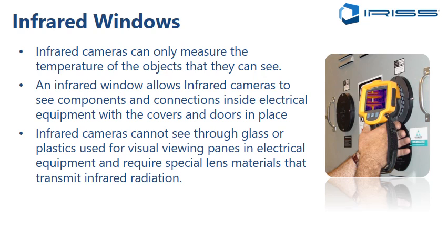Now, infrared cameras cannot see through glass or plastics, and this is a common misconception. The visual viewing panes that your eye can see through, an infrared camera can't see through them because they don't enable the infrared radiation to transmit through them. So we need special lenses and materials that enable that infrared radiation to pass through the lens, so we can make a reading using the infrared cameras.